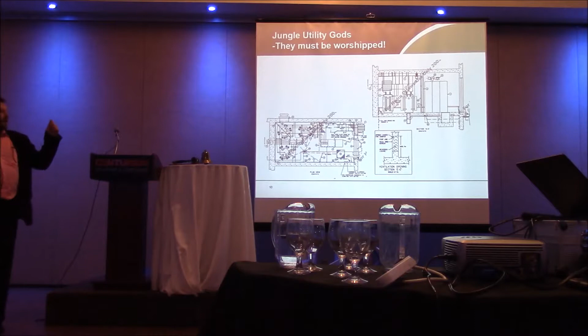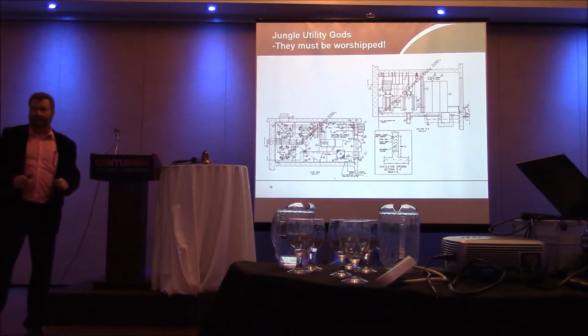Beyond your own guidelines for getting rid of heat, since you calculate so many cubic feet per minute based on average temperature to remove the heat we need to get rid of, the utility will have a number that's a lot higher. Find out what it is. They're very conservative. So despite your calculation being accurate with some fat added to cover it, find out the utility's required airflow rate through the vault and meet that requirement. Because if you don't meet it, they won't turn your vault on. Which means delay to the contract, changes to the fan, and a change order.